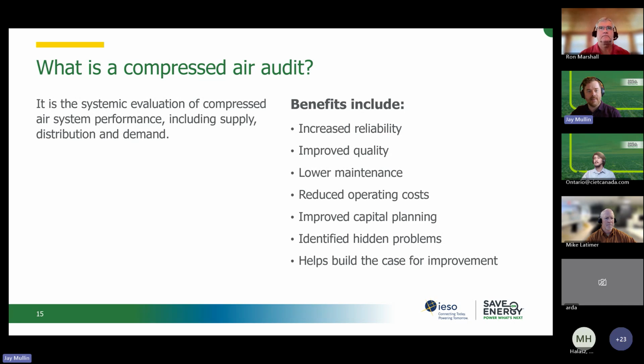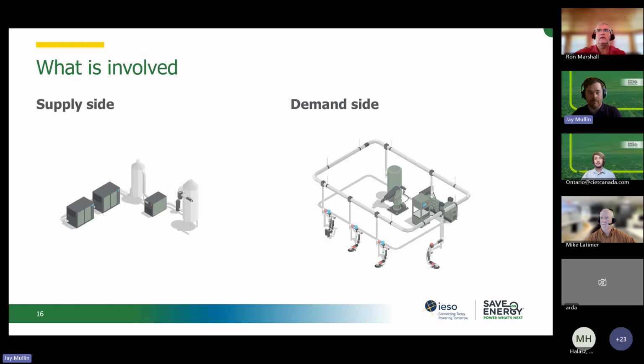Before we get into the details of what's involved in the audit, I want to make sure we're all on the same page about what it is. When we talk about a compressed air audit, we're talking about a systemic evaluation of your compressed air system performance that includes looking at supply, distribution, and demand. As Ron mentioned, there are lots of benefits beyond reduced operating costs. The supply side is the equipment that supplies the compressed air, including compressors, dryers, storage tanks, all of that. Then everything on the demand side includes the distribution pipes, end uses like those hoses, the presses that use the air, and even what the compressed air is used for. Is compressed air the right use for that application? All of that's part of the demand side.